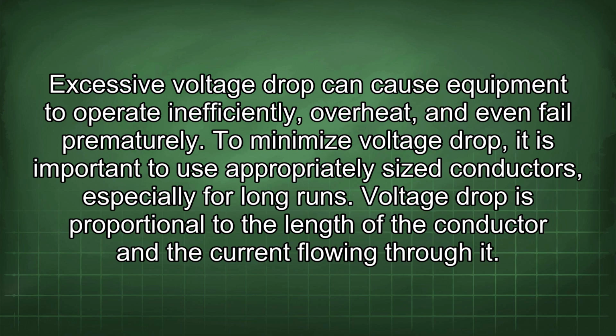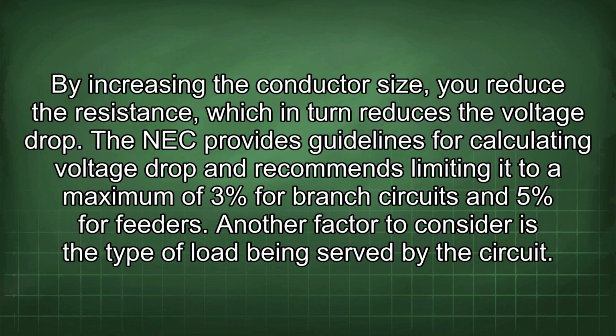To minimize voltage drop, it is important to use appropriately sized conductors, especially for long runs. Voltage drop is proportional to the length of the conductor and the current flowing through it. By increasing the conductor size, you reduce the resistance, which in turn reduces the voltage drop. The NEC provides guidelines for calculating voltage drop and recommends limiting it to a maximum of 3% for branch circuits and 5% for feeders.